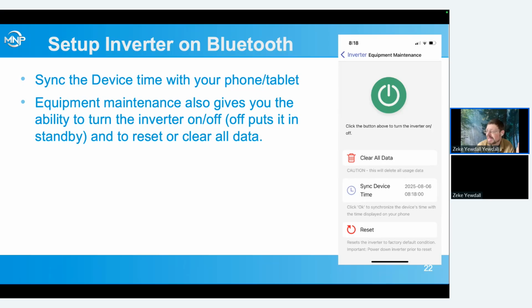So once you get all the rest of the settings where they're correct and there's no errors, especially like CT settings and such, it's sometimes a good idea to then go in and clear all the data so it can start out from good settings and not have some bad data there at the beginning of it. Reset resets everything to the factory defaults. If you've gone through and changed a whole bunch of stuff and you're just not sure what you've changed and it's just not working right, sometimes going back to the factory defaults is a good place to get you back to where you know where you're starting.